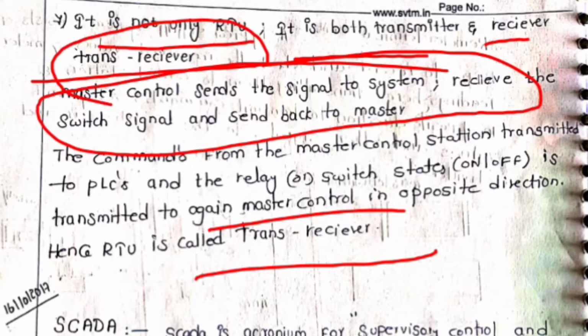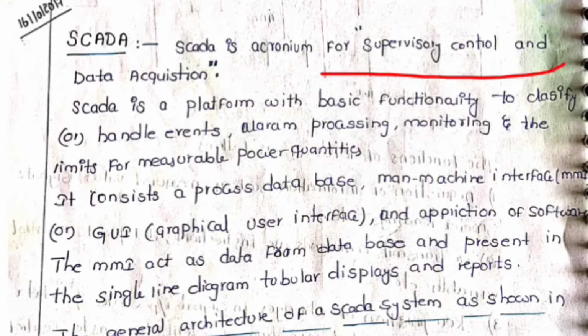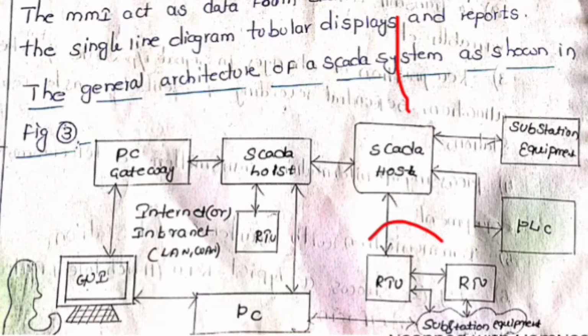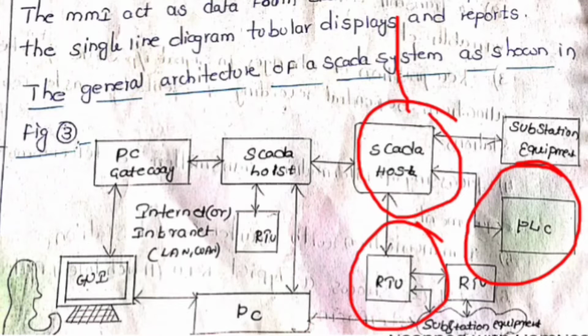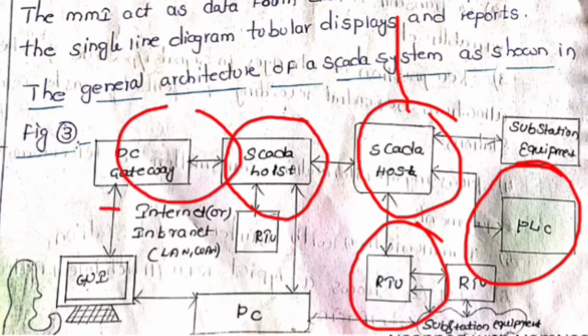Coming to the SCADA system, everybody knows what SCADA is: Supervisory Control And Data Acquisition. SCADA is a platform with basic functionality to handle events, alarm processing, monitoring, and limits of measurable power qualities. Power quality can be enhanced by using a SCADA system. A typical SCADA system consists of various parts: the RTU is the main part in the SCADA system, along with many PLCs, SCADA host computer, SCADA host gateway, PC gateway, and the person who can monitor.